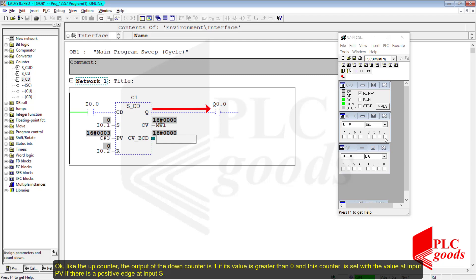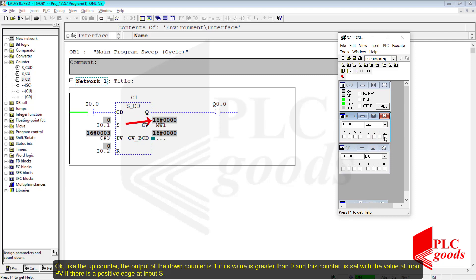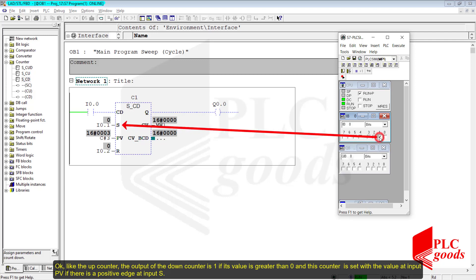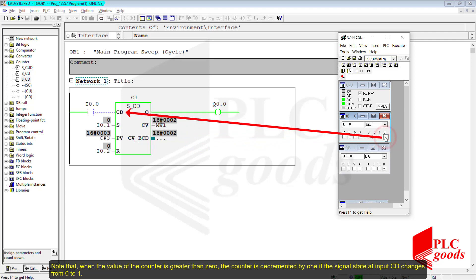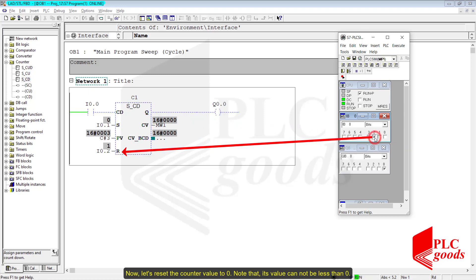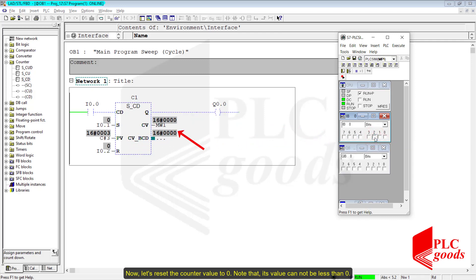Like the up counter, the output of the down counter is 1 if its value is greater than 0. This counter is set with the value at input PV if there is a positive edge at input S. When the value of the counter is greater than 0, the counter is decremented by 1 if the signal state at input CD changes from 0 to 1. Let's reset the counter value to 0 — note that its value cannot be less than 0.